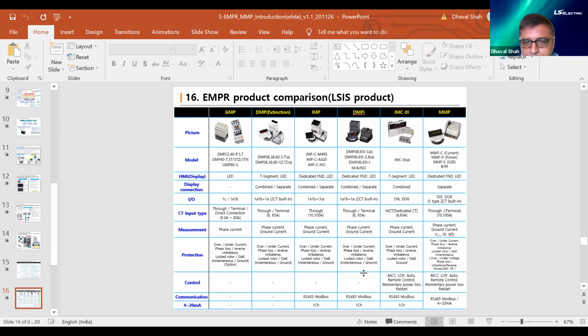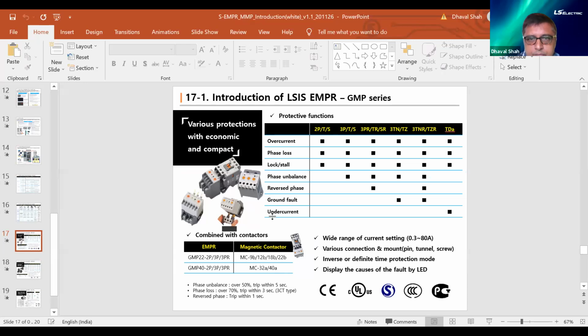And of course, in the new upcoming models, we are trying to accommodate communication also. So these are the variants. When we go for GMP, there is tunnel type, screw type, and ZCT is inbuilt. If you see, overcurrent is there, lock. When we go for Z type, ground fault is available. When we go for R type, the reverse phase protection is available. When we go for this TDA model, you get undercurrent protection also inbuilt.